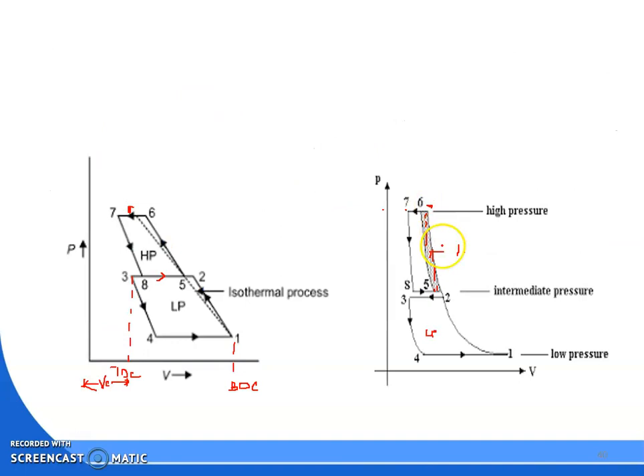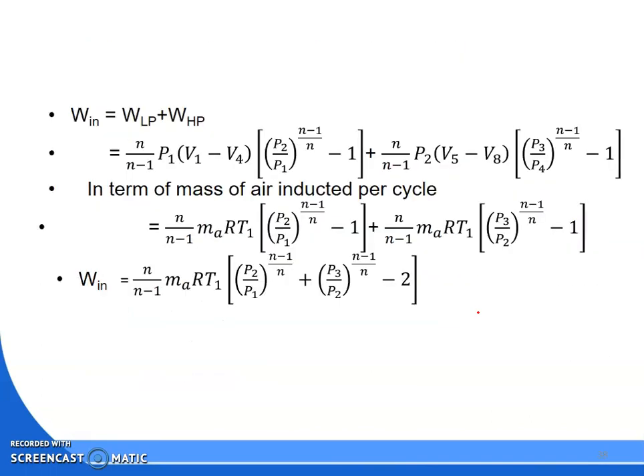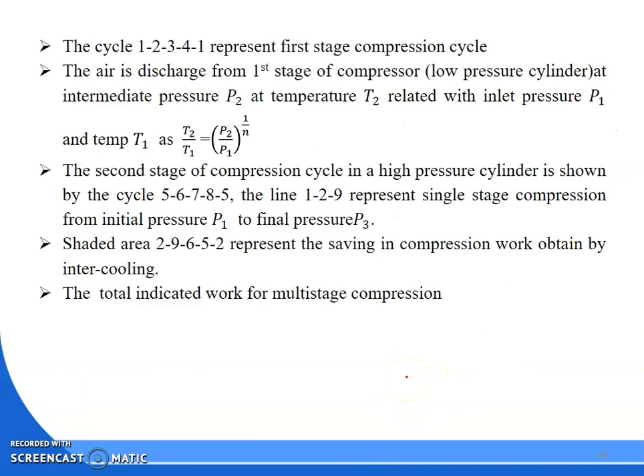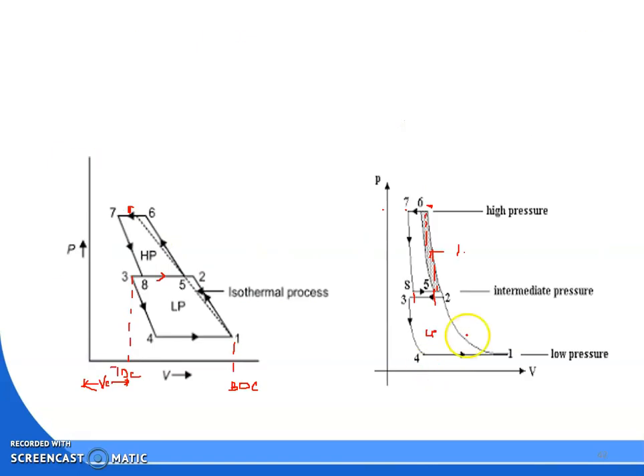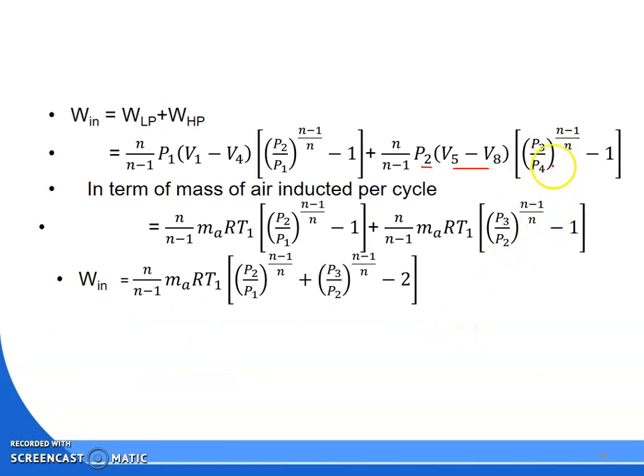For the high-pressure cylinder, the effective swept volume is (V5 - V8). The pressure at the inlet of the high-pressure cylinder is the intermediate pressure P2, and pressure increases from P2 to P3. Since the intercooler resets the temperature back to T1, the work for the high-pressure cylinder is: W = [n/(n-1)] × mRT1 × [(P3/P2)^((n-1)/n) - 1], where P3 is the delivery pressure and P2 is the suction pressure of the high-pressure stage.